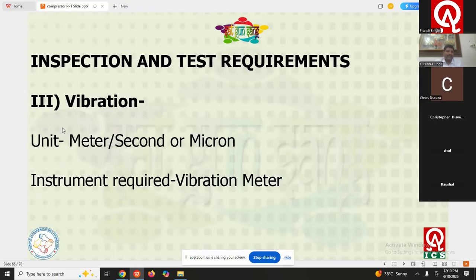If we are going to check the vibration, then we need an instrument. The unit is meter per second or micron. So there are two methods to check the vibration. Either we can check in meter per second or micron. API 618, 619, or 672 clear cut state that you have to check the vibration in meter per second, which we discussed in previous slides. For that measurement, we need the instrument as vibration meter.